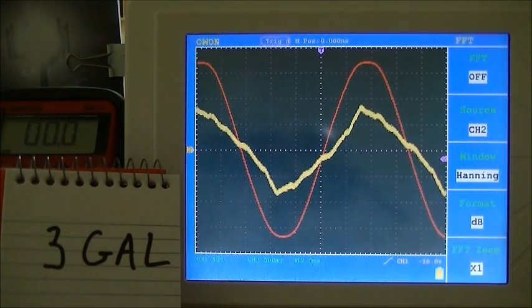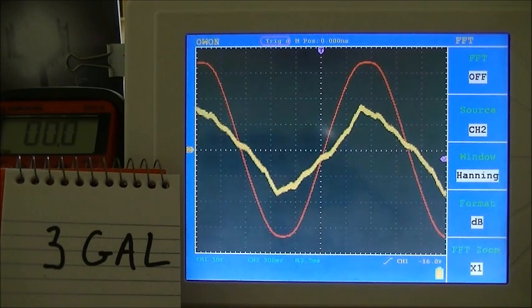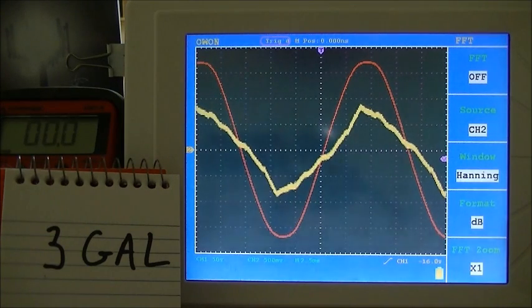As you can see, watering the ground rods didn't really appear to do much and it's something that I've suspected for a while. Whether your ground rods are wet or dry, what determines the level of stray voltage on your system is what the utility company is doing. This is very clearly coming from the utility company neutral system as I've actually disconnected my fuse board from the system and I still see the same voltage on the utility company neutral at the meter.